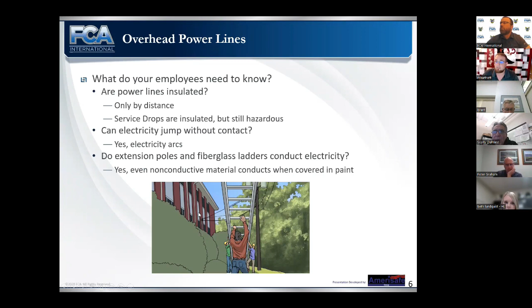So in this picture, you see these lower lines, and these are generally communication lines, but the lines coming off these little transformer cans going into the facility, those are your secondary lines, and those are going to be energized. So how close can you get? You can get on most of what you're dealing with 10 feet. Right, so 50 kV is 50,000 volts, right? So all distribution level, everything on those wooden poles for the most part, is going to be 10 feet away. But as that voltage gets higher into transmission, those distances get farther.